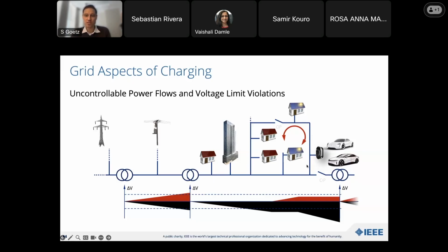But that might overload, for example, some lines here, and the voltage can do weird things that the grid operator only sees indirectly through state estimation. And right, the first problem is already that you easily leave the tolerance voltage band. Right? Injection increases the voltage, power you draw reduces the voltage. But it should stay within a plus minus 10% limit, but this is until your socket in the wall. That means that many grid operators want to keep it within plus minus 5%.